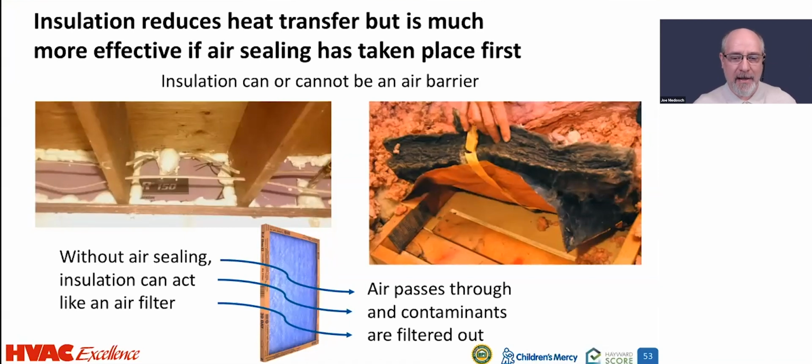But the Manual J has one component that's called infiltration, and it's trying to determine how much you think the home leaks. And those are usually guessed, or you could use a blower door to determine that. But infiltration can sometimes be 20, 30, 40% or more of the size of the equipment. And that's where we're going to try and focus, between actually having a good thermal boundary that's aligned with your air barrier.